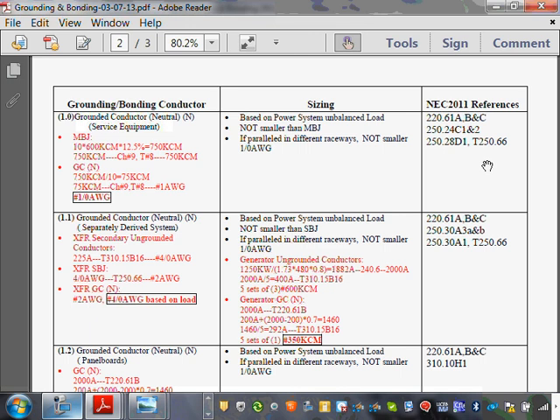Okay, so you know why I did not multiply: 2000, then from the 2000 divided by 5, I want to pull 5 sets. I sized 5 sets of 3 conductors, 600 kcmil. Why 3 phase? Then what I do with the neutral, guys, is, that's the 3 phase. Then I take my neutral, I take the 2000 amp exactly, and I apply this rule 220.61(B) on it.